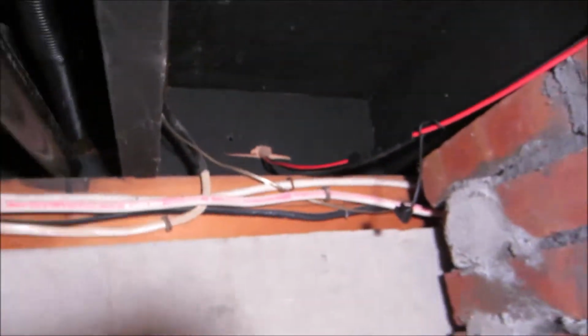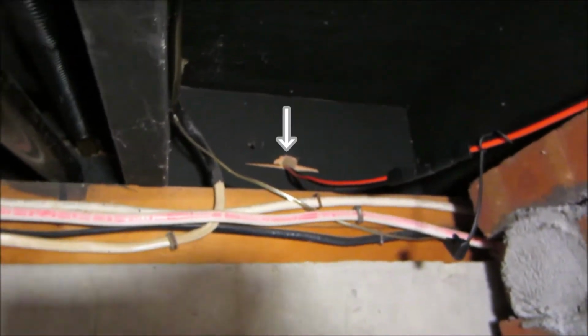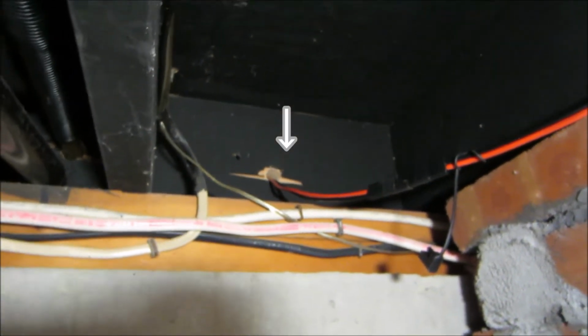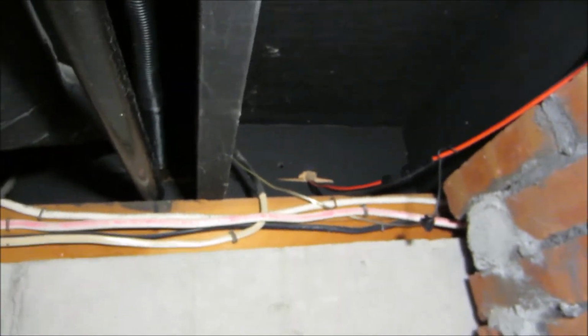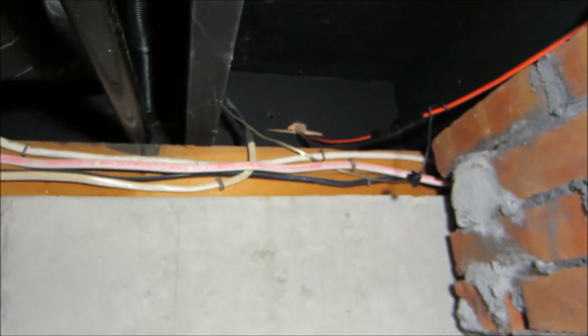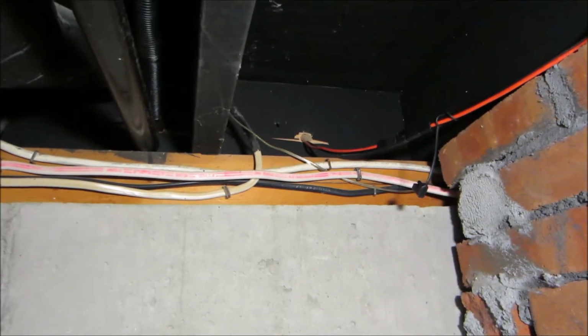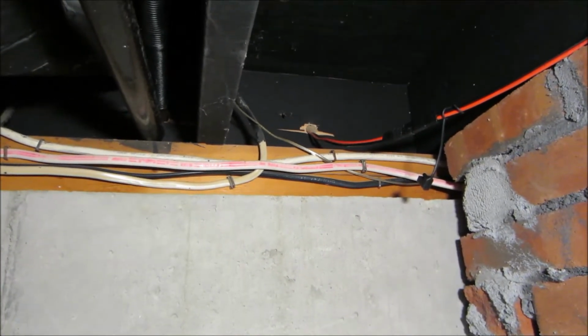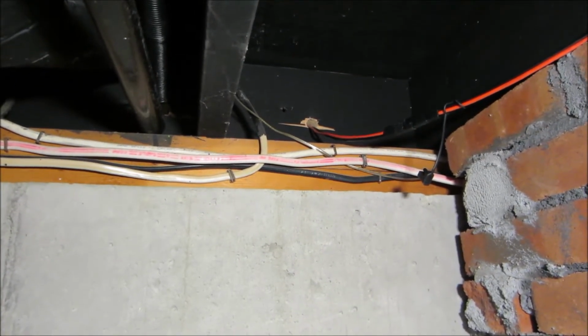Here is the back of the sidewall connector right up there that we put in, that we showed on the outside of the house. Now the reason it's so difficult, or the reason you're so easily tricked by reverse polarity gotchas, is because the sidewall connector would be the very first thing you put in.